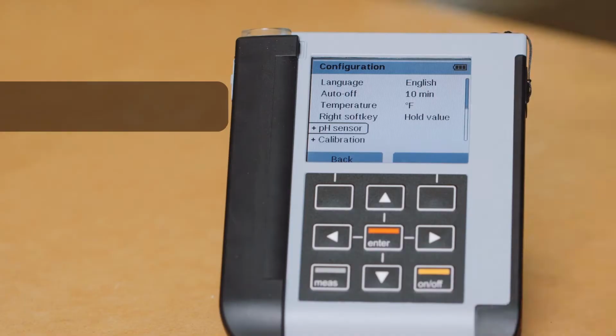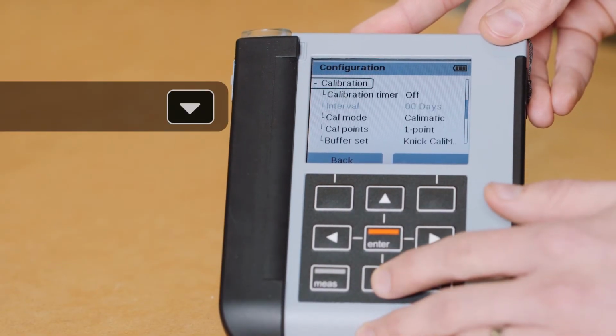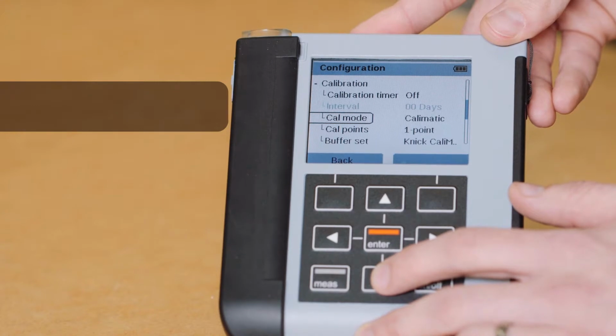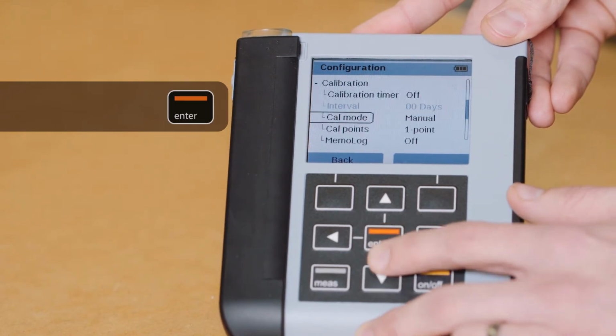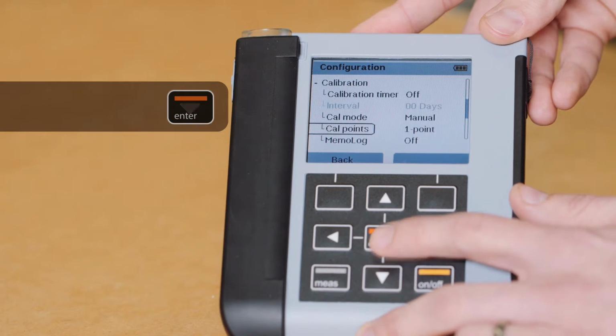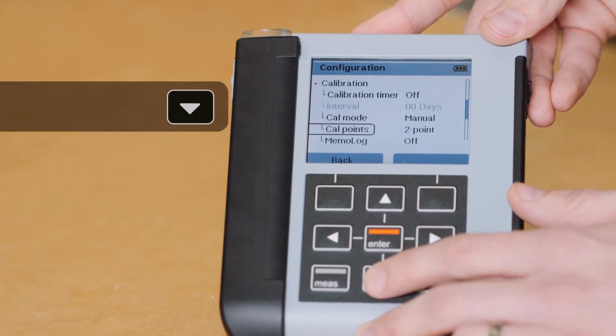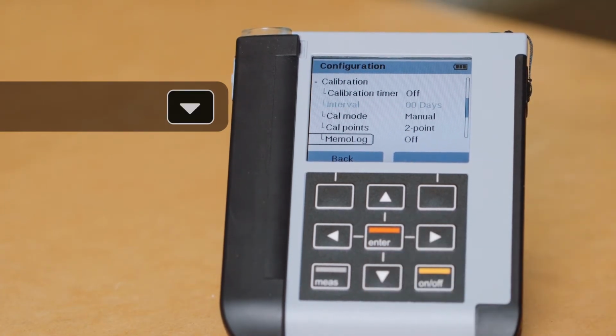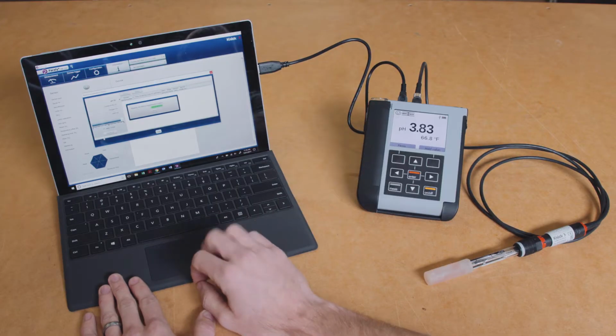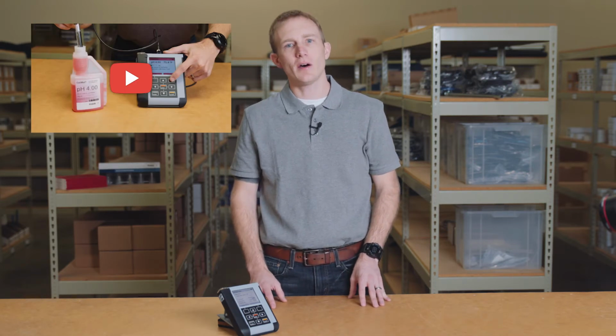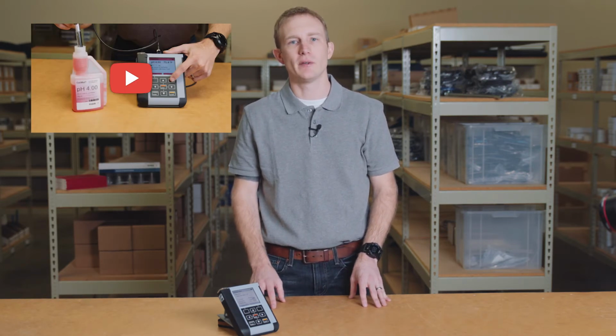Next is setup of the calibration menu. The options here are dependent upon the type of sensor which you have connected. For a pH sensor, we can select the type of calibration, whether it is automatic or manual. We can also select the number of points for our calibration, as well as turning on or off MemoLog. MemoLog allows you to collect the last 100 calibrations in your Portavo, which can then be exported into our software through the USB cable. You can find out more about this in our calibration video on the Portavo 907 Multi.